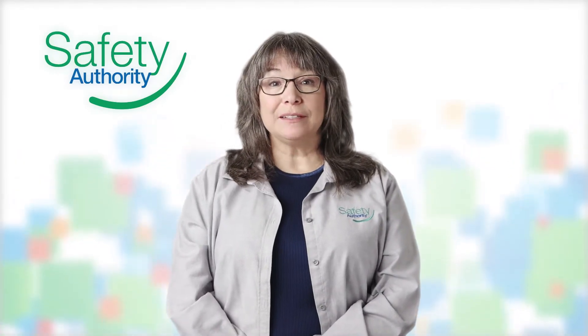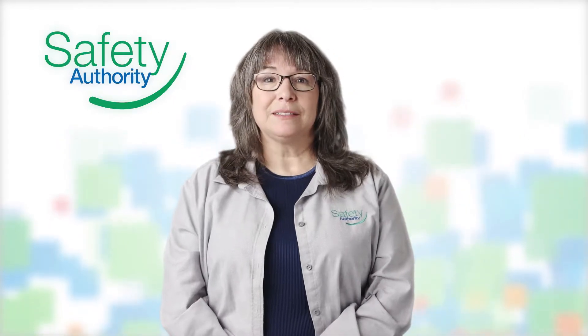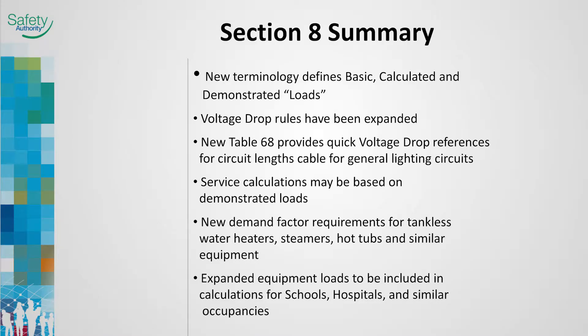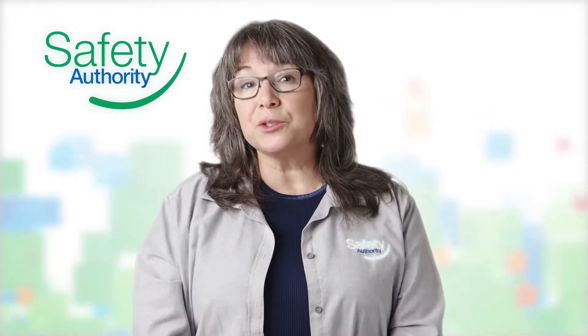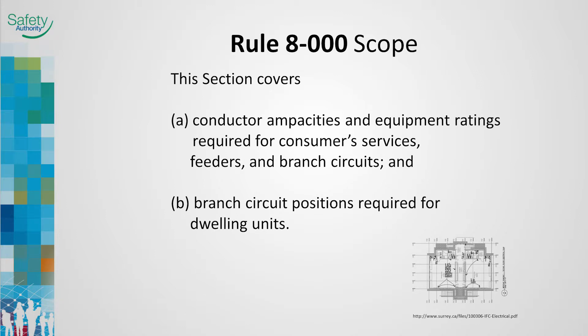Here is a Section 8 summary. New terminology defines basic, calculated and demonstrated loads. The voltage drop rules have been expanded. A new Table 68 provides quick voltage drop references for lengths of general lighting circuits. Service calculations may be based on demonstrated loads. New demand factor requirements for tankless water heaters, steamers, hot tubs and similar equipment. Expanded equipment loads to be included in calculations for schools, hospitals and similar occupancies. Remember, Section 8 does not cover all specific loads and the branch circuits which supply them. For example, you'll find motors in Section 28 and the electric heating loads in Section 62.